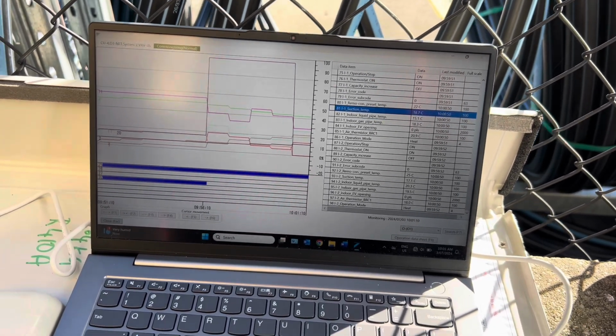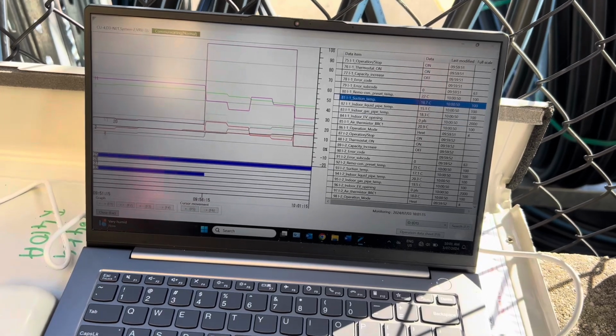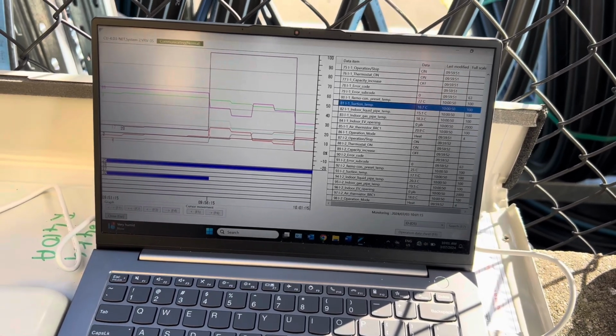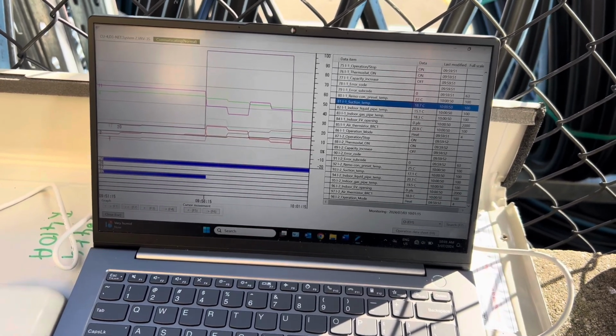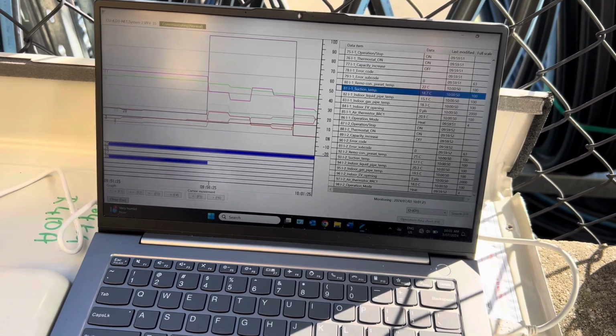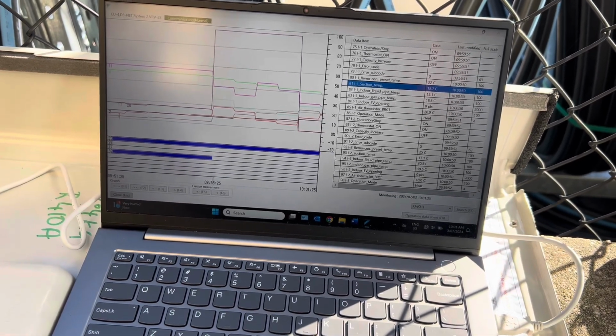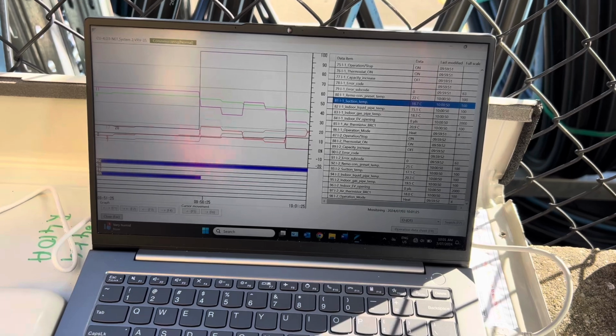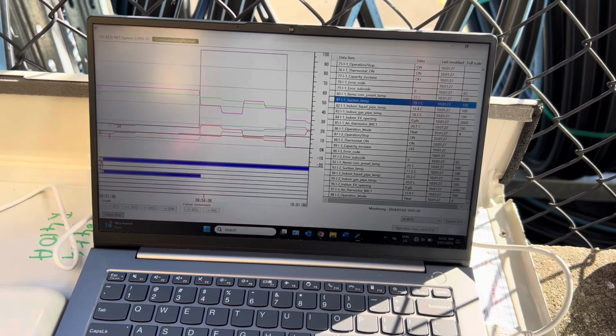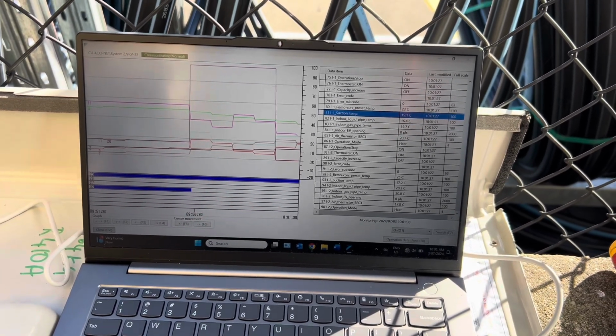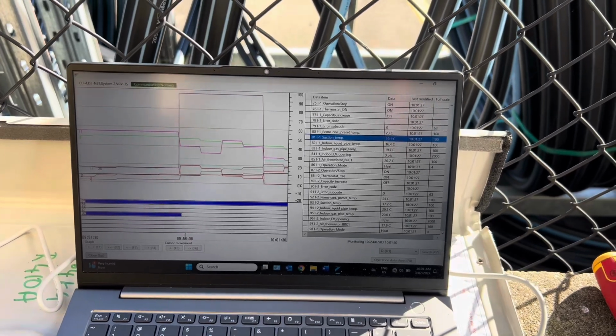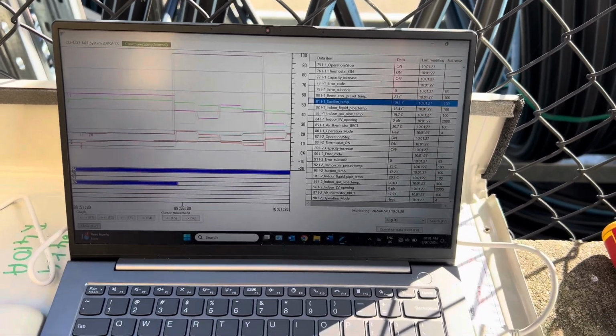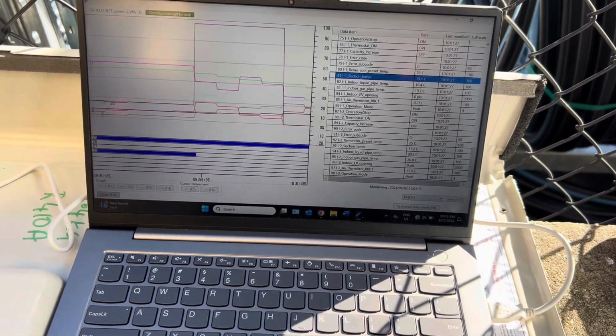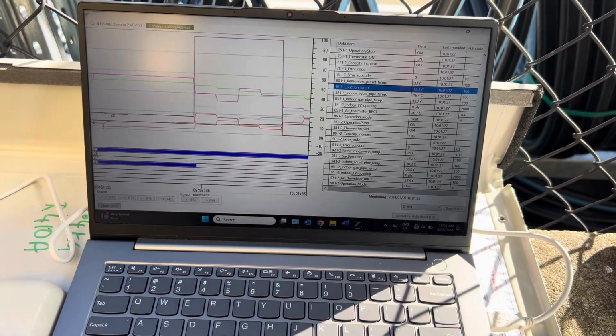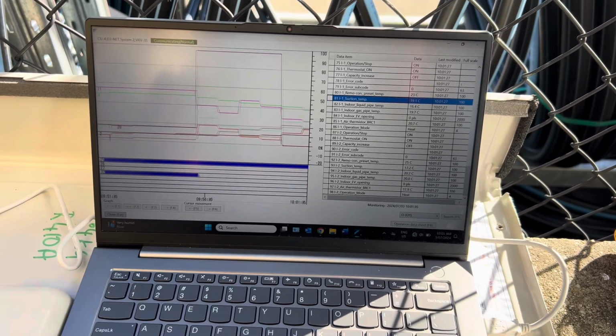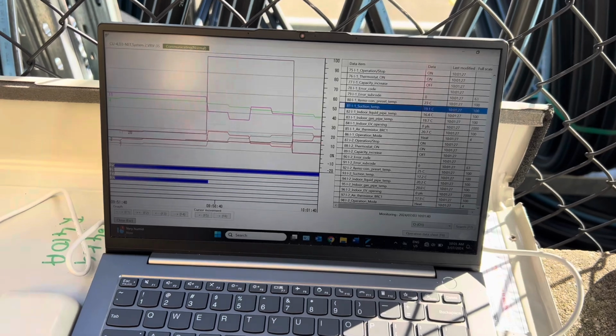Now the byproduct of that is that other system in the lunchroom, which also has the door open, is constantly cold. Because it's wanting to run in heating mode the entire time, but it's dictated by the other controller. So it's constantly sitting at 17 degrees even though the set point is 25, and that system is also going into heating and cooling. It's obviously not cooling because it's 17 degrees and set for 25, but it's just going into cooling mode and circulating that 17-degree room temp air.